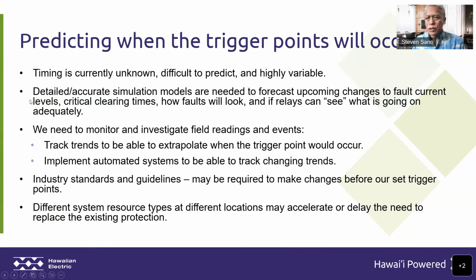Predicting when these trigger points will occur, this next slide sort of summarizes what our current thinking is on this. Timing is currently unknown, very difficult to predict, and highly variable. Detailed, accurate simulation models are needed to forecast upcoming changes to fault current levels, critical clearing times, how fault currents look, if the relays can see what's going on adequately. Our simulation models are getting better.